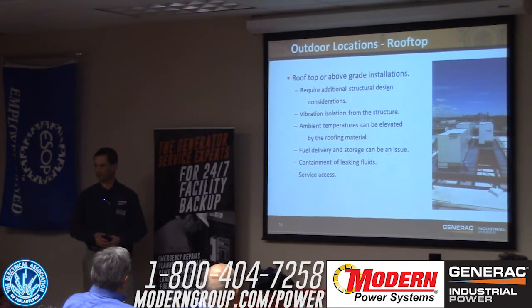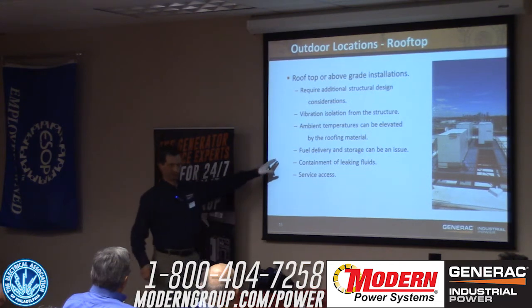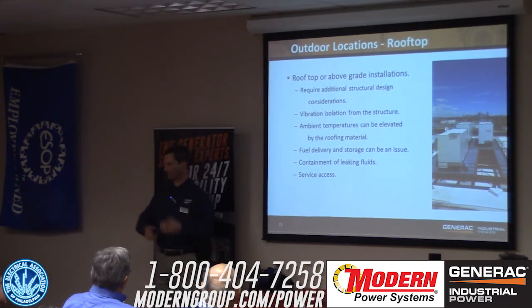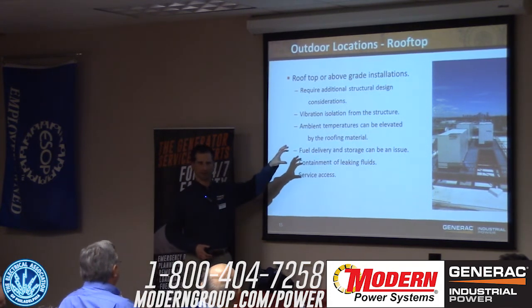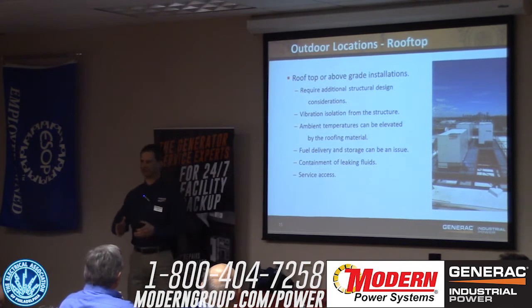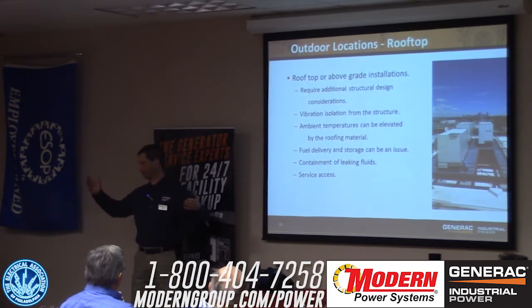It'll be a little warmer up there because of the roofing material. If it's a diesel, there will be some type of fuel storage and a fuel transfer pump system up top—a main tank down below and a limited amount of fuel up top, typically at least 2 hours. If you're in New York City or other jurisdictions, or if there's a fire pump involved, you're looking at a minimum of 6 hours. That's another requirement with some variability to it.